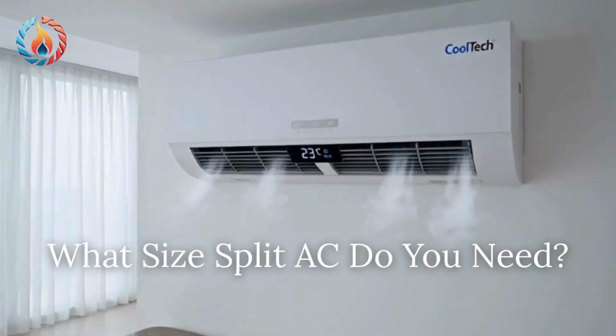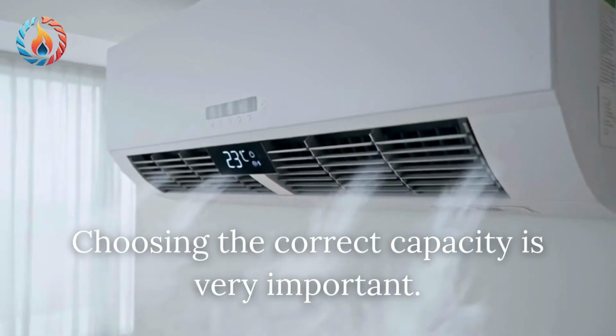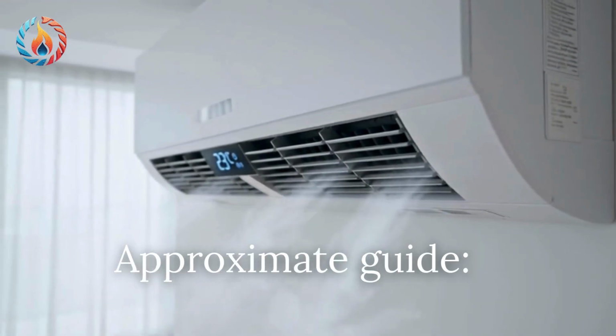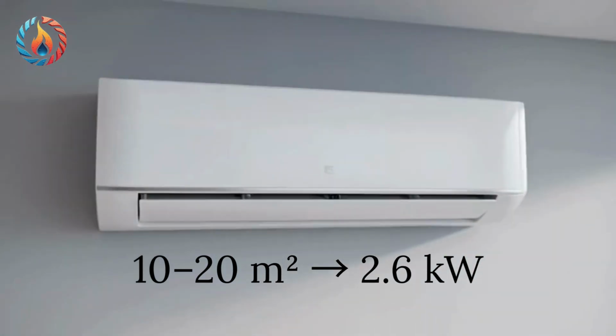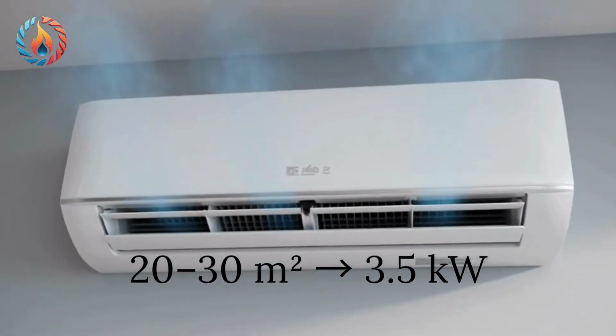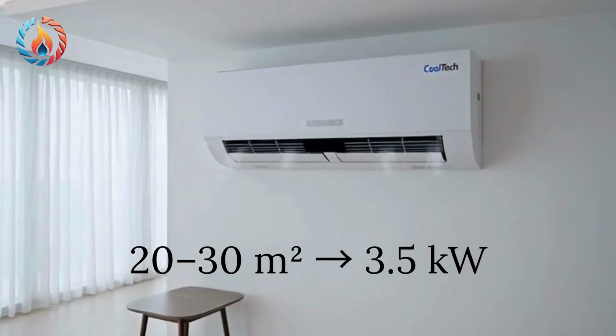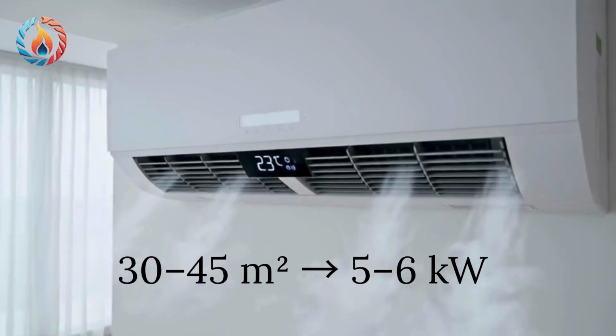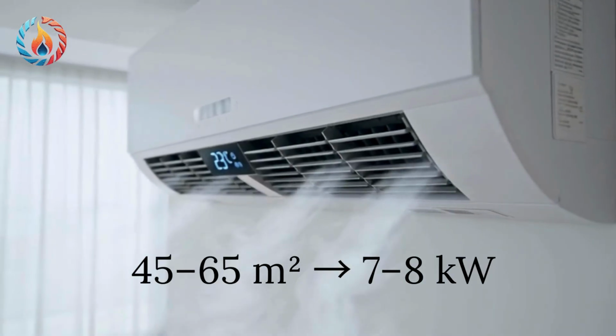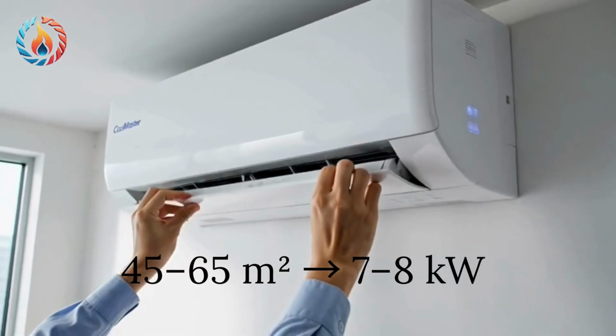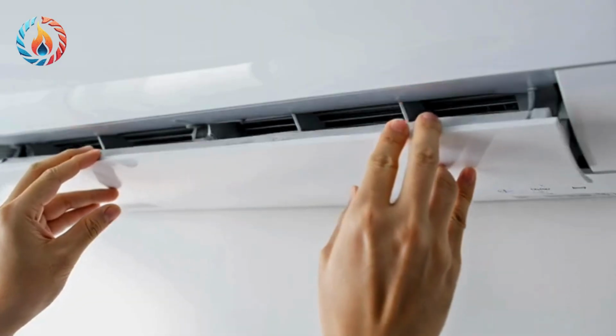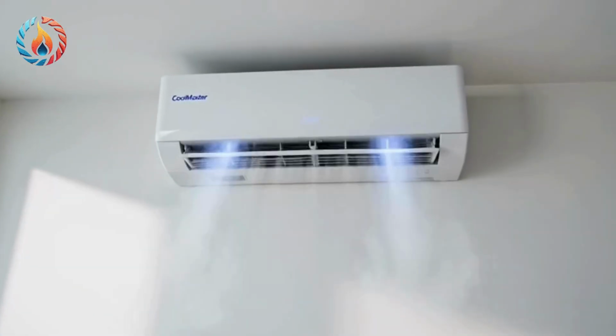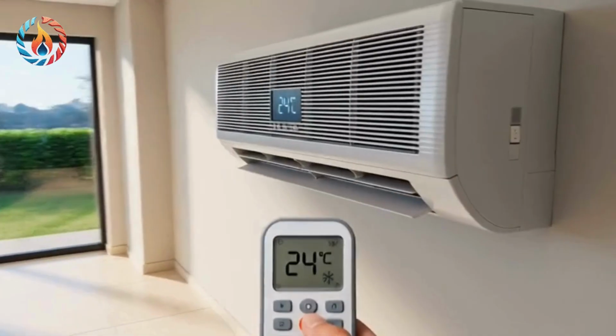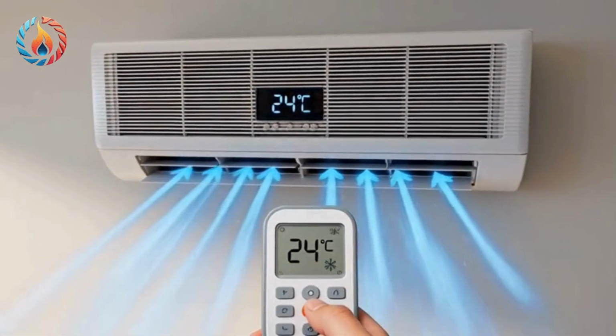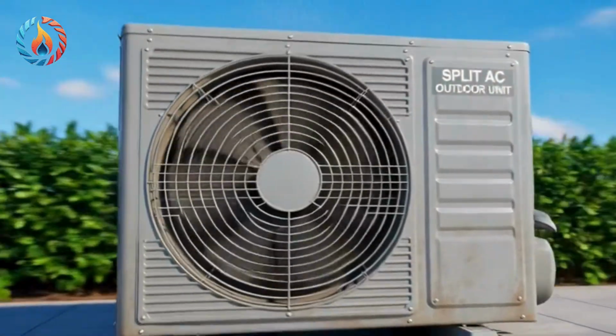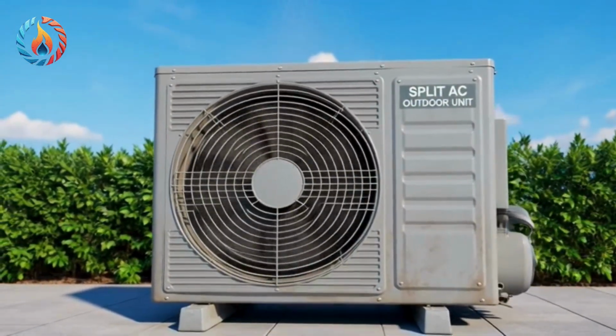What size split AC do you need? Choosing the correct capacity is very important. Approximate guide: 10 to 20 m², 2.6 kilowatts. 20 to 30 m², 3.5 kilowatts. 30 to 45 m², 5 to 6 kilowatts. 45 to 65 m², 7 to 8 kilowatts. Factors affecting size selection: room size, insulation quality, sun exposure, and room orientation. An oversized unit wastes energy, and an undersized unit will not cool properly.